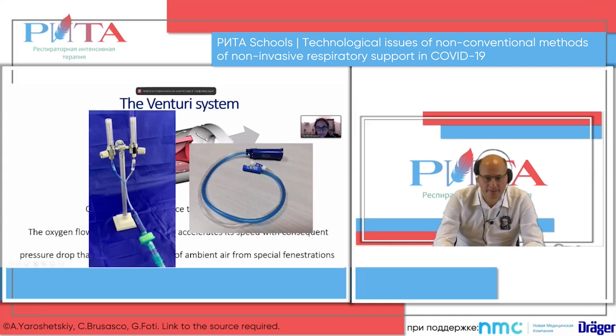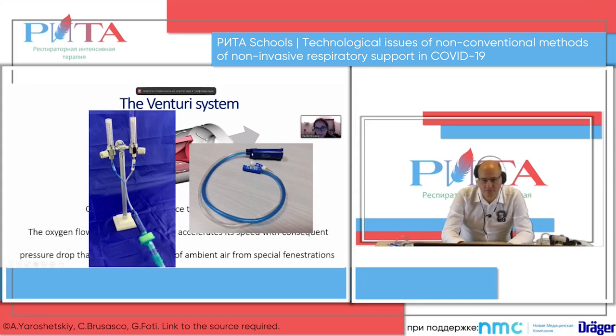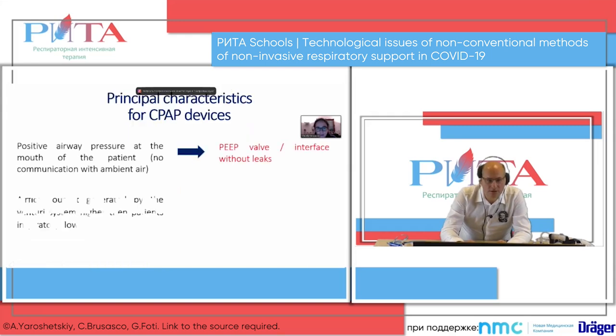Okay, this is the Venturi system we are looking at. The Venturi is this black and blue part. The oxygen arrives from the blue channel and gets narrowed. From here it sucks the ambient air, okay? From here it gets ambient air. You see, they are parallel, all working the same way, and this makes a very good acceleration of the oxygen flow. So I put 15 liters from here, and I get 120 here. And I can show you, wait.